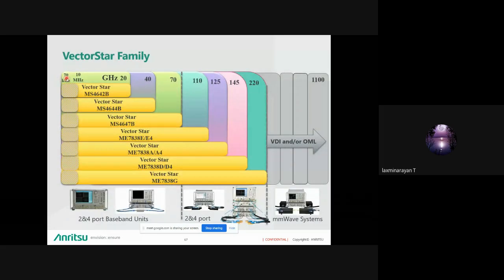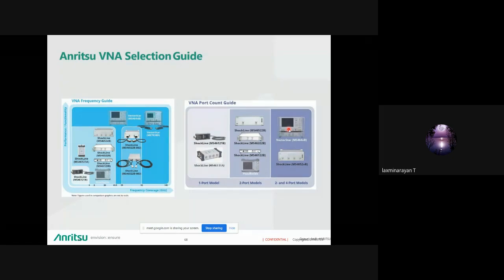We have models starting from 70 kilohertz, and going to 20, 40, 70, 110, 125, 145, 120, 220 gigahertz and 1.1 terahertz. Using a VDI and OML modules, we can extend up to 1.1 terahertz, with 2 and 4 ports, and it also supports millimeter wave systems. For frequency selection, we have up to 145 gigahertz in the VectorStar, 55 to 92 in the ShockLine series, and at 43.5 gigahertz we have both VectorStar and ShockLine series VNAs.